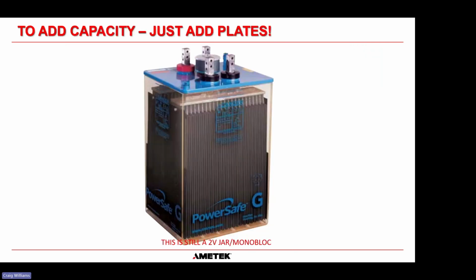And then to add capacity, all you need to do is add more plates. So you can see here now we have 1 through 22, so this is probably a 25-plate battery. Now remember that this is still a 2-volt cell, it's actually a 2-volt monoblock or a 2-volt jar. So this will only give you 2 volts, but adding all of these plates together gives you more surface area, which gives you more capacity.